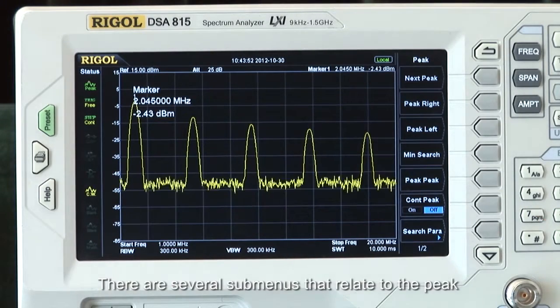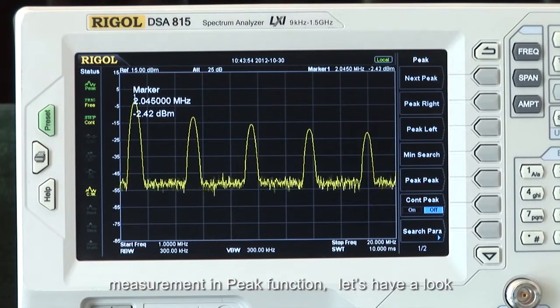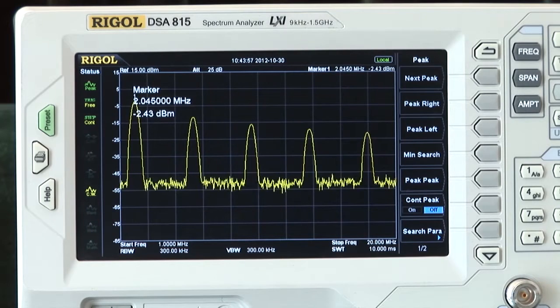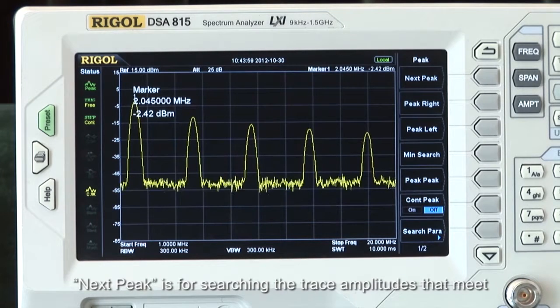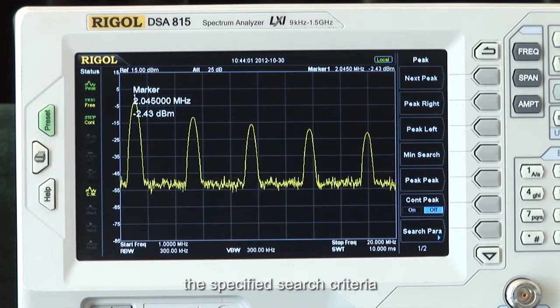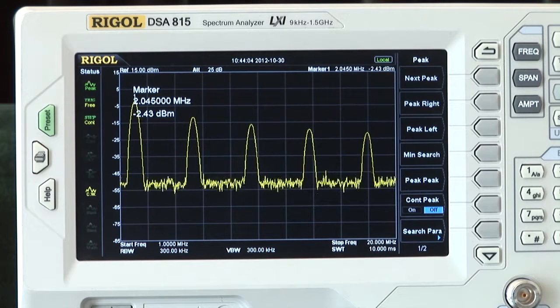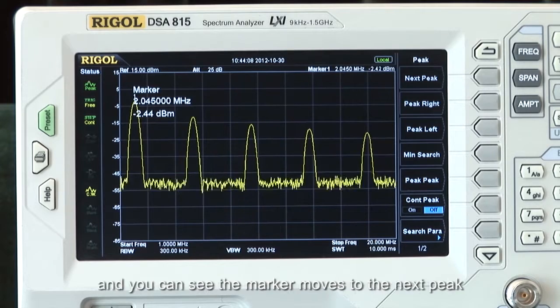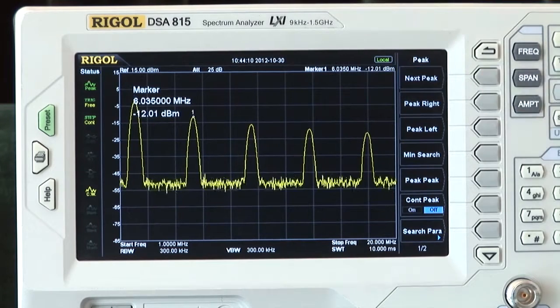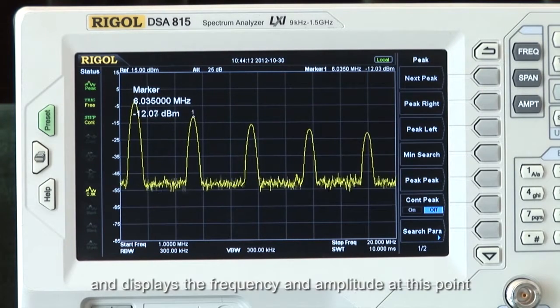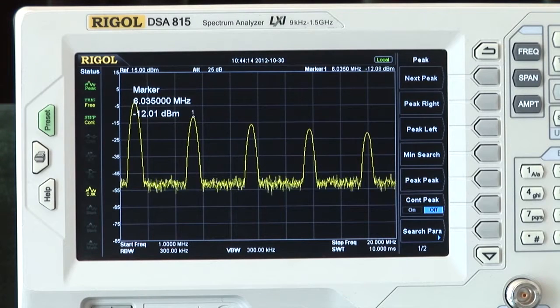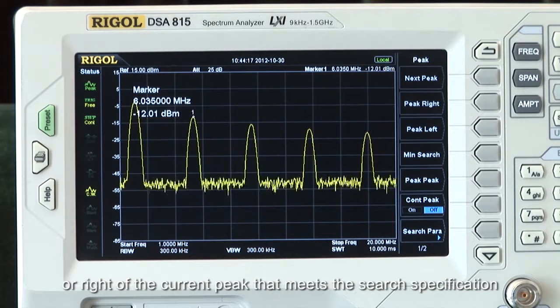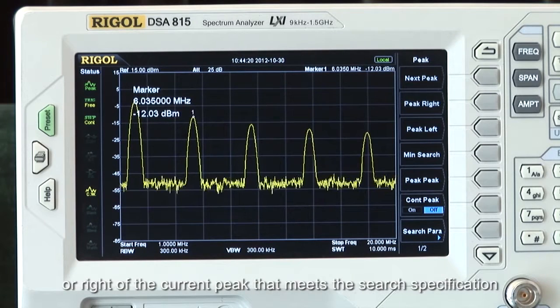There are several submenus that relate to the peak measurement in peak function. Next Peak is for searching the trace amplitudes that meet the specified search criteria. Press Next Peak, and you can see the marker moves to the next peak and displays the frequency and amplitude at this point. Peak Left or Peak Right will search for the peaks to the left or right of the current peak that meet the search specifications.